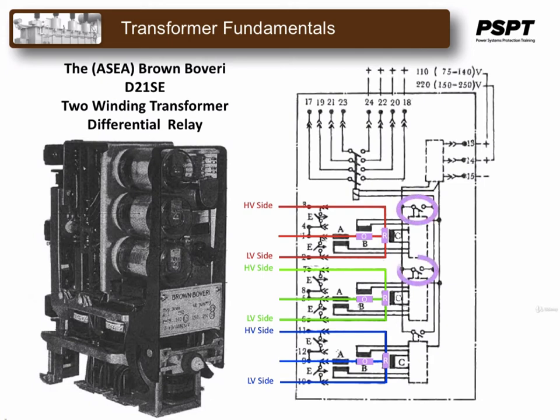Each of these operating coils will pick up a high speed contact that is designed to bring in the 110 or up to 240 volt DC control tripping mechanism for any breakers that would be required to isolate the transformer, and this will pick up an auxiliary relay with multiple contact outputs. It's simple and effective and carries out the function of a restraint differential relay.